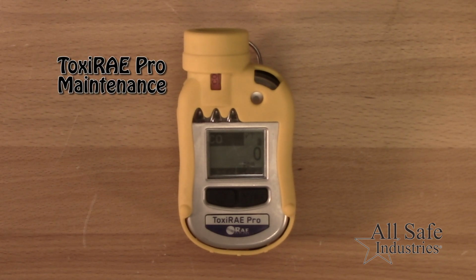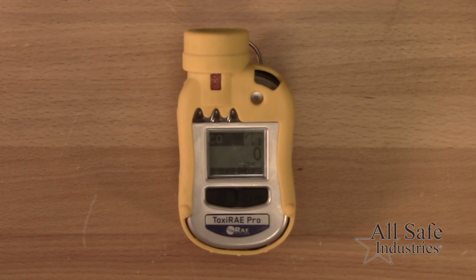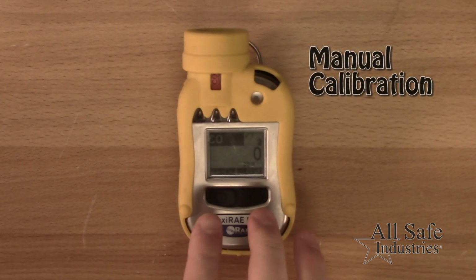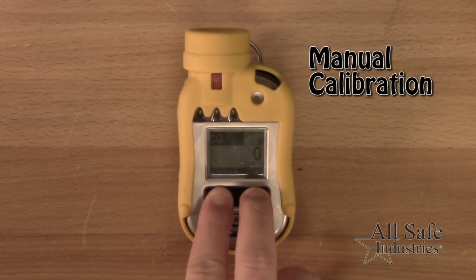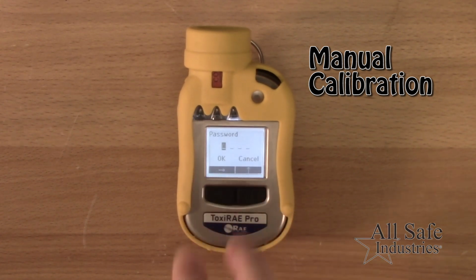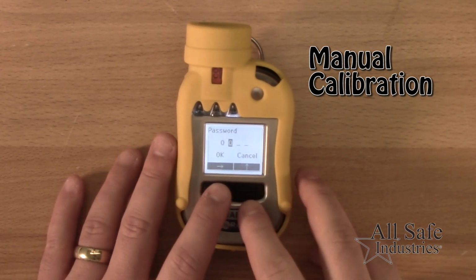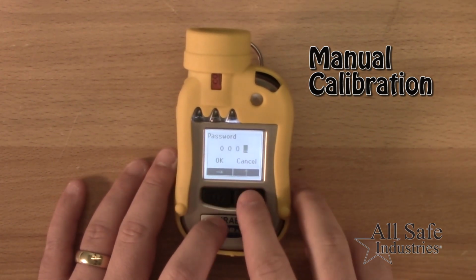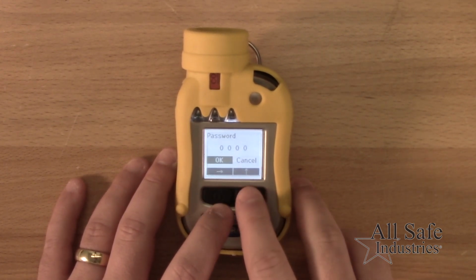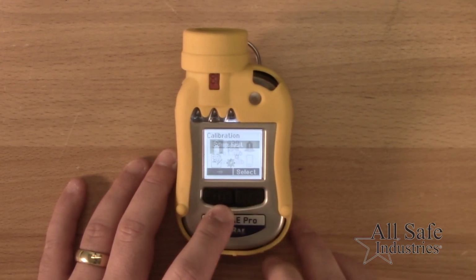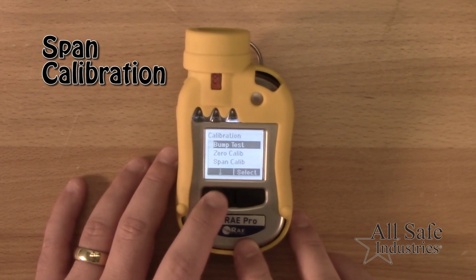This quick video will show you basic maintenance for the ToxiRAE Pro. To perform a calibration, press and hold both the mode key and the Y+ keys to access the menus. Enter the 4-digit password of 0000 and select OK. Select the calibration menu and then select the span calibration sub-menu.